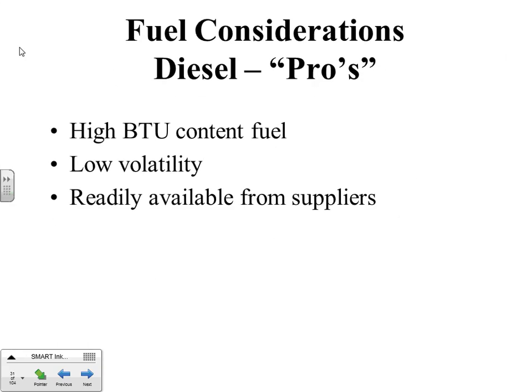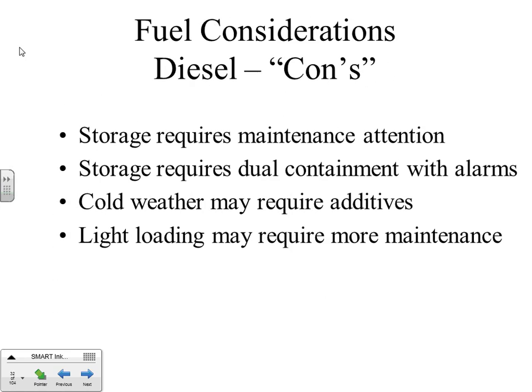Okay, moving away from the gas system into diesel. The pros for diesel, it's a high BTU content fuel. It's got low volatility. Doesn't ignite real easy. So it's slippery though. And it's readily available from suppliers. On the con side for diesel, the storage requires some maintenance attention because after several months of sitting in a tank, it will start to do some bacterial growth in it, so it requires some maintenance.